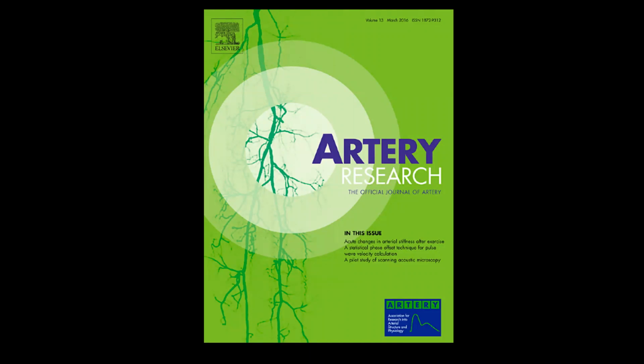But the problem is that you go to a range of individuals, and you're going to be calibrating the device against different arterial mechanics. If you have an elderly person with a calcified artery, you may not be able to apply the data acquired on another individual. It will be all of the different rigidities of the arterial tree that occur with aging, hypertension, and other diseases that will prevent you, I think, from taking data from healthy individuals and saying, I can use that function and infer what the blood pressure is. So I guess that is the next step.